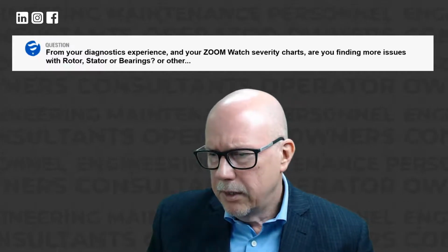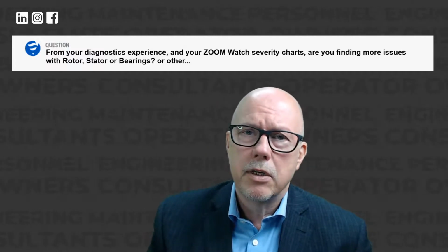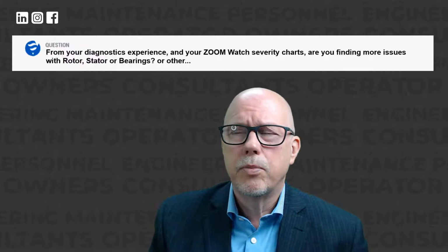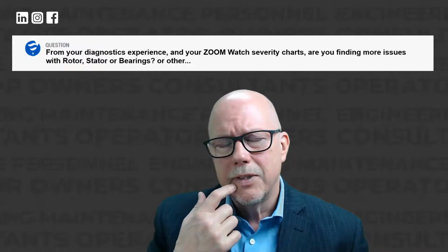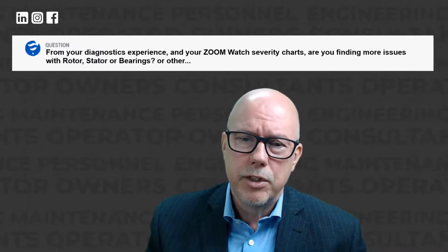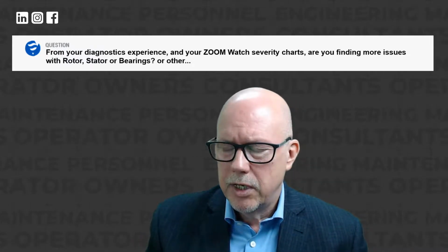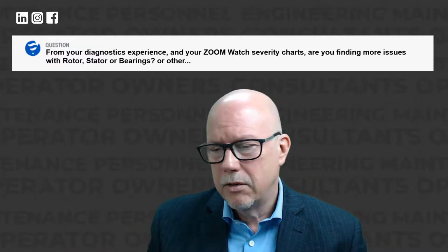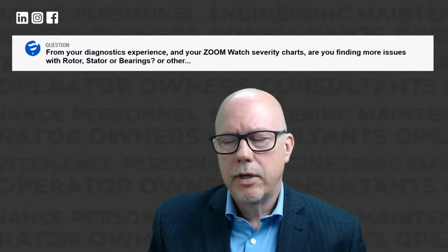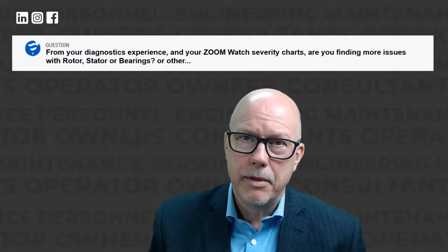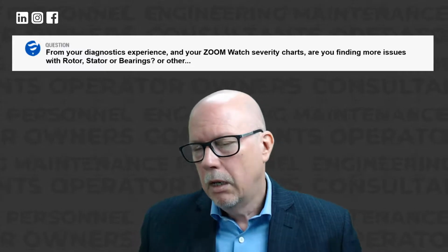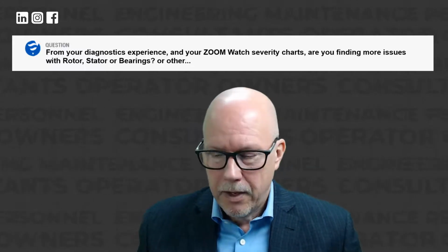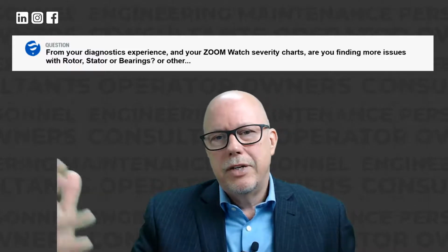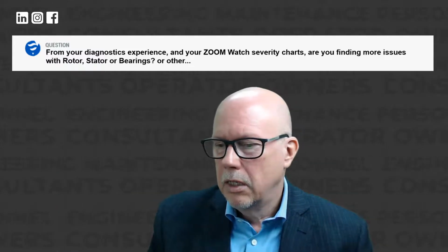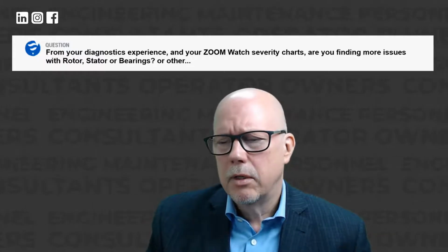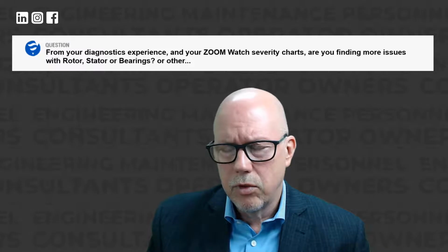But I think the biggest issues we find — and maybe we emphasize this because it's a rotating part — are in rotors, rotor poles, and rotor rims. My department pays very close attention to that, because if there's an issue, the fact that it's rotating and subjected to centrifugal forces and strong electromagnetic forces means things can go very wrong quickly and cause tremendous damage. Whereas a seized sole plate on a stator is an issue, usually easy to solve, but it's not going to cause major damage to the unit, not in the short term. So I'd say we see more serious issues with the rotors.